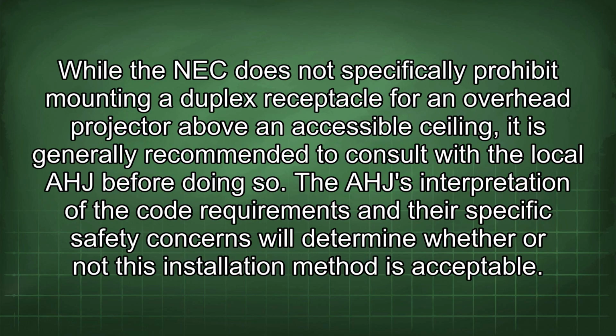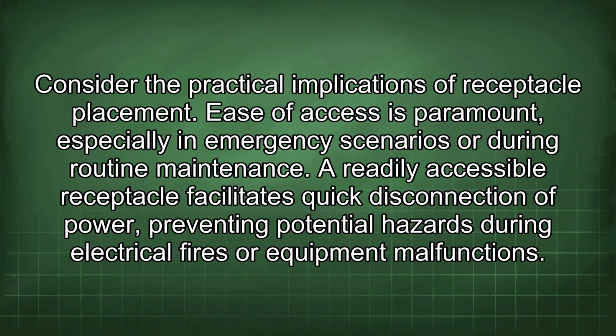While the NEC does not specifically prohibit mounting a duplex receptacle for an overhead projector above an accessible ceiling, it is generally recommended to consult with the local AHJ before doing so. The AHJ's interpretation of the code requirements and their specific safety concerns will determine whether or not this installation method is acceptable. Consider the practical implications of receptacle placement. Ease of access is paramount, especially in emergency scenarios or during routine maintenance. A readily accessible receptacle facilitates quick disconnection of power, preventing potential hazards during electrical fires or equipment malfunctions.